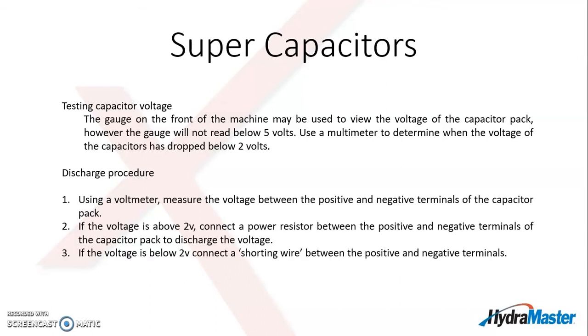So the discharge procedure: using again the gauge on the front of the machine or a voltmeter, measure the voltage between the positive and negative terminals on the capacitor pack or the positive and negative bus bars on the controllers. If the voltage is above 2 volts, then you need to connect a power resistor between the positive and negative terminals to discharge the capacitor pack fully. If the voltage is below 2 volts, it's recommended that a shorting wire be installed between the positive and negative terminals. That prevents any voltage from building up in the capacitor pack.